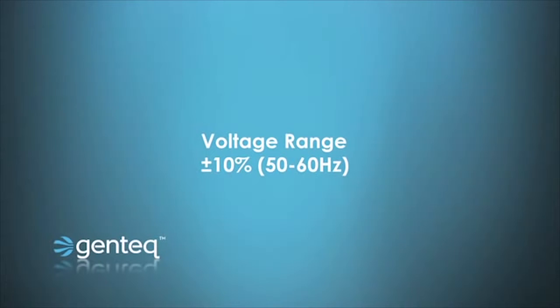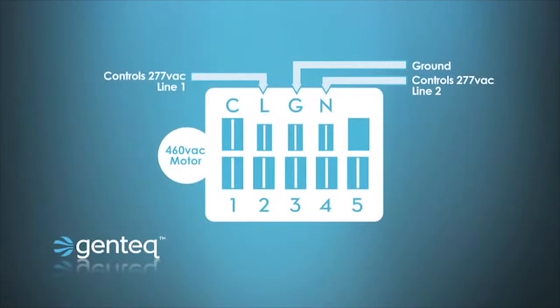It is also important to note that these are not dual voltage motors. One is built at 115 volts and one is built at 230. And on the new 460 volt, again, L stands for line 1, G would be for ground, and N would be line 2.